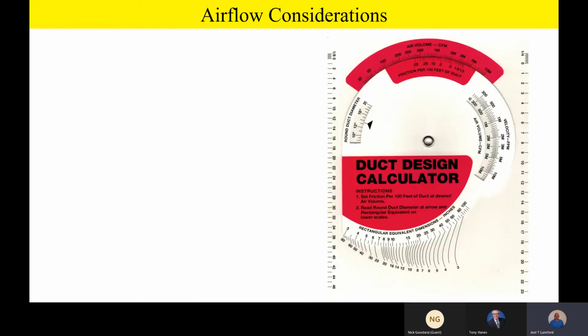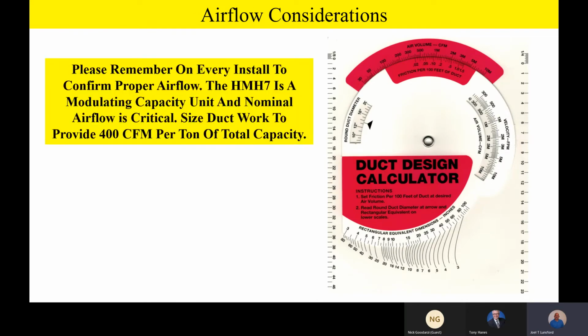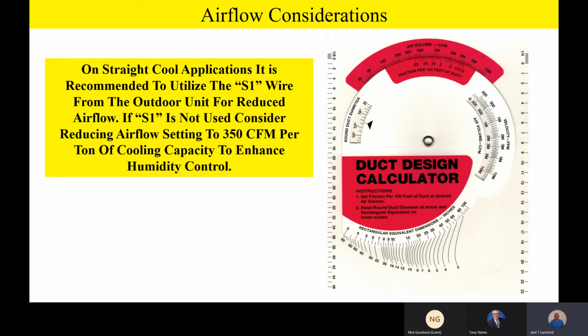Team, at this time, let's talk a little bit about airflow considerations. There's a couple things, again, I want to stress with that. The first thing is, please remember on every install to confirm proper airflow. The HMH7 is a modulating unit, and nominal airflow is going to be critical. We're going to ask that all ductwork be sized to provide 400 CFM per ton of total cooling on the ductwork side. Now, on a straight cool application, it's recommended to utilize the S1 wire from the outdoor unit for reduced airflow. That's our standard recommendation.